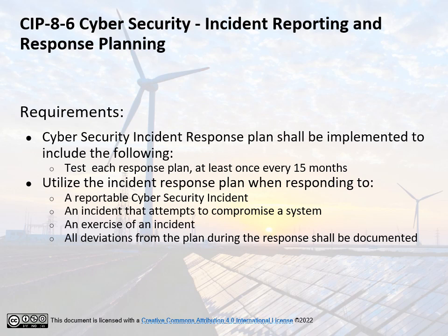CIP-008-6 Incident Reporting and Response Planning. Requirements: the cybersecurity incident response plan shall be implemented to include the following. Test each response plan at least once every 15 months by responding to an actual reportable cybersecurity incident or with a paper drill, tabletop exercise, or an operational exercise. Utilize the incident response plan when responding to a reportable cybersecurity incident, an incident that attempts to compromise a system, or an exercise of an incident. All deviations from the plan during the response shall be documented.